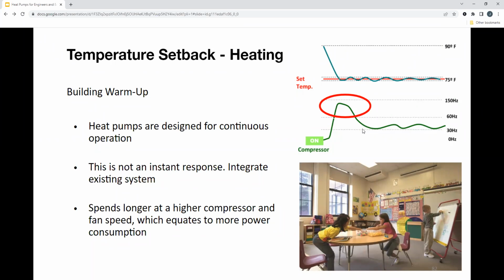But I would recommend, if you are trying to do temperature setback, stick to 5 degrees or less for a temperature setback, because you're really trying to get away from ramping this compressor up. We're really trying to just keep it at a steady compressor speed.